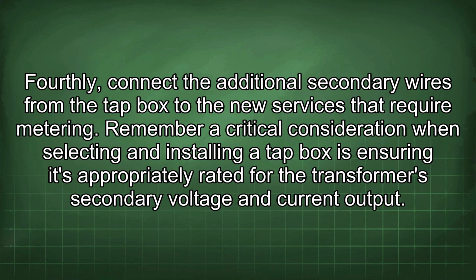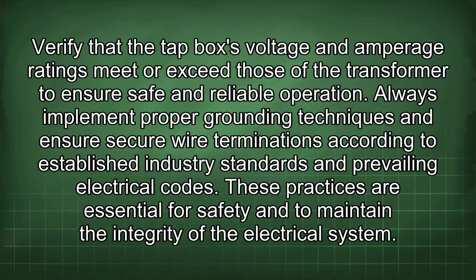Remember, a critical consideration when selecting and installing a tap box is ensuring it's appropriately rated for the transformer's secondary voltage and current output. Verify that the tap box's voltage and amperage ratings meet or exceed those of the transformer to ensure safe and reliable operation. Always implement proper grounding techniques and ensure secure wire terminations according to established industry standards and prevailing electrical codes. These practices are essential for safety and to maintain the integrity of the electrical system.